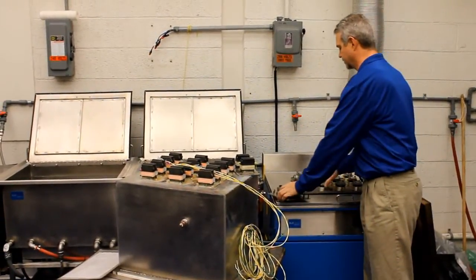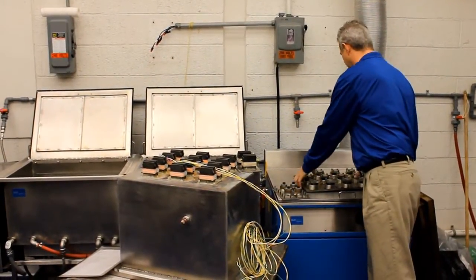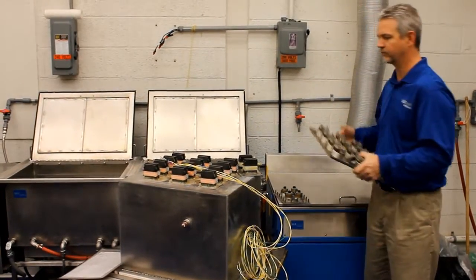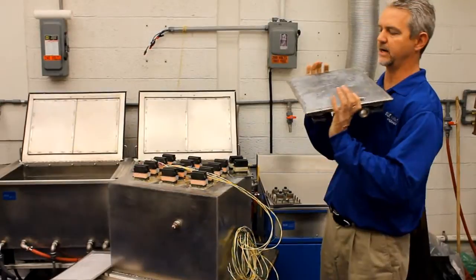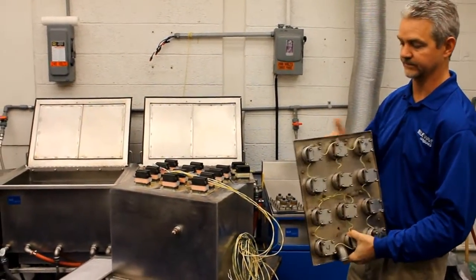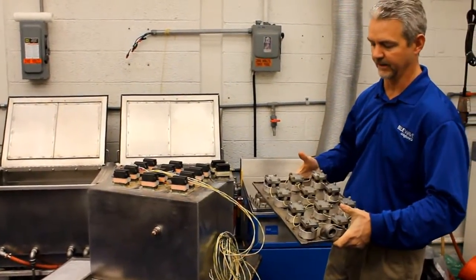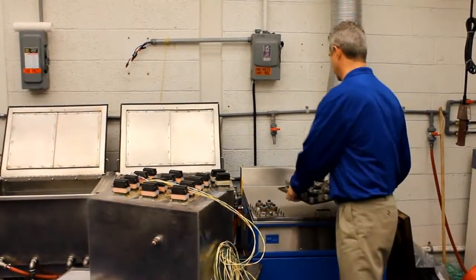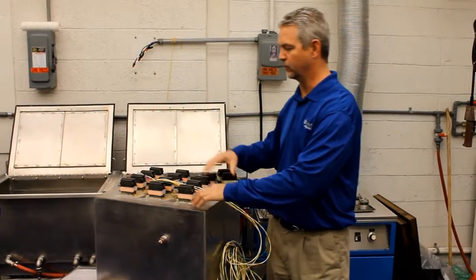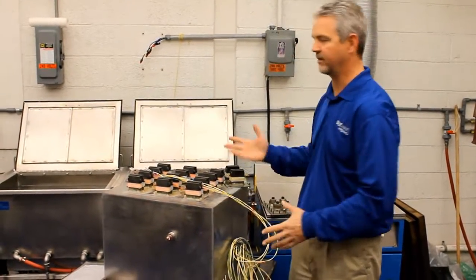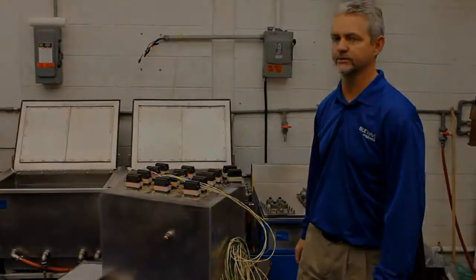This is a transducer assembly that we actually removed from one of our local customers. We cut it out of the bottom of the tank because it just didn't provide enough energy to create cavitation anymore. We cut it out, used our existing tank, and welded in a new radiating diaphragm assembly, and the tank is as good as new.